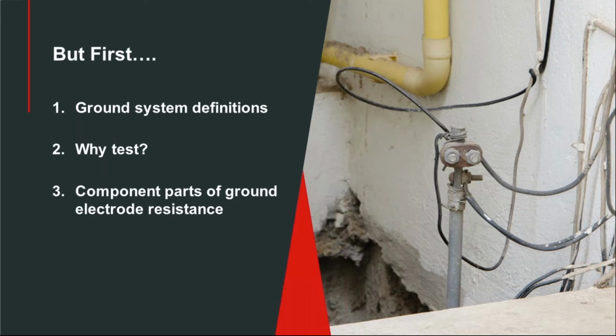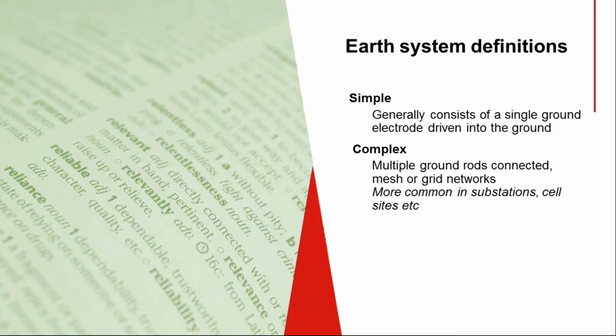The rods erode away underground, they rust, they erode in other manners. Fault clearance, very energetic faults, and lightning strikes can clear perfectly well, with no damage to your building, and you think everything went great. And it did, except that the grounding electrode is not in the same condition it was before it cleared the fault, because it can self-destruct in the process. So you want to test your ground to make sure it meets spec when installed, and test it periodically thereafter to make sure nothing is eroding or being damaged.